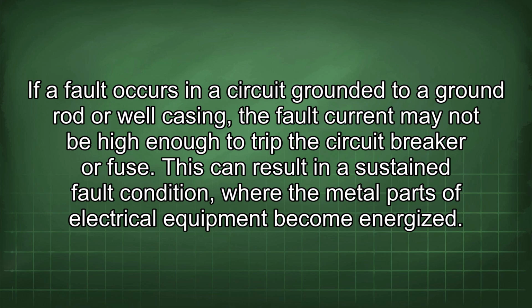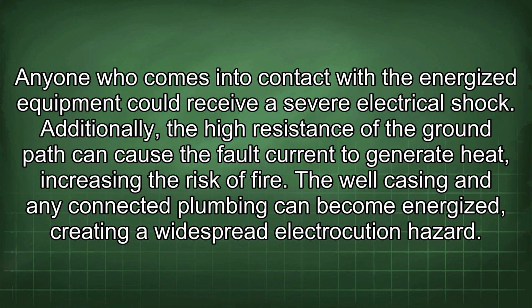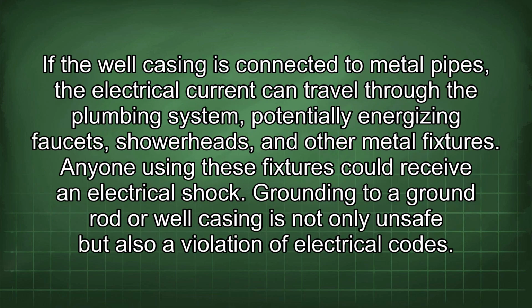If a fault occurs in a circuit grounded to a ground rod or well casing, the fault current may not be high enough to trip the circuit breaker or fuse. This can result in a sustained fault condition where the metal parts of electrical equipment become energized. Anyone who comes into contact with the energized equipment could receive a severe electrical shock. Additionally, the high resistance of the ground path can cause the fault current to generate heat, increasing the risk of fire. The well casing and any connected plumbing can become energized, creating a widespread electrocution hazard. If the well casing is connected to metal pipes, the electrical current can travel through the plumbing system, potentially energizing faucets, shower heads, and other metal fixtures. Anyone using these fixtures could receive an electrical shock.